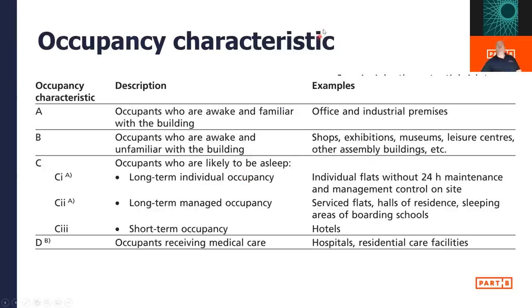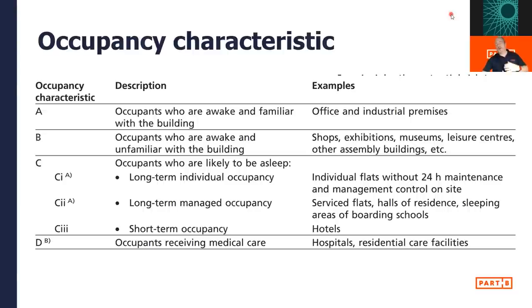The first thing we look at is the occupancy characteristic, which forms part of our risk profile. There are four: A, B, C, and D. Occupancy characteristic A — occupants who are awake and familiar with the building, typically places where people are employed, such as office and industrial premises. These people are trained, told what to do in the event of fire, and are pretty disciplined. They hear a fire alarm test every week, go through fire drills every year or six months, and know where the fire assembly point is.